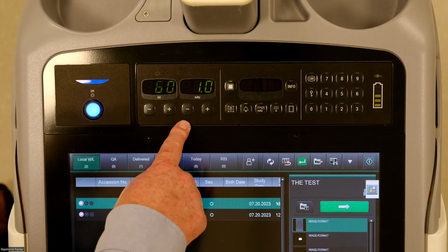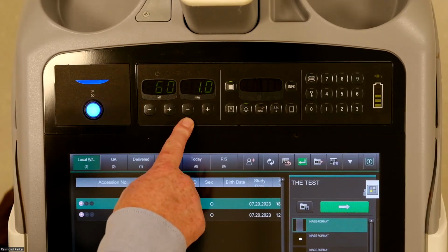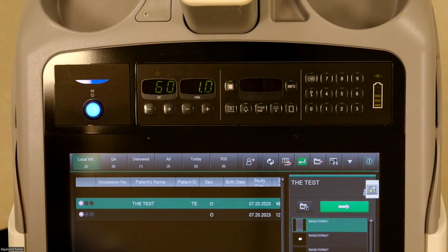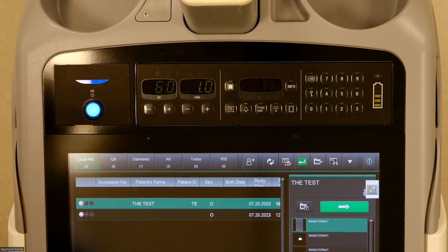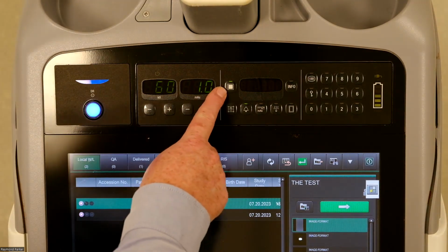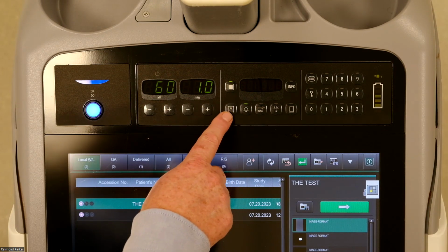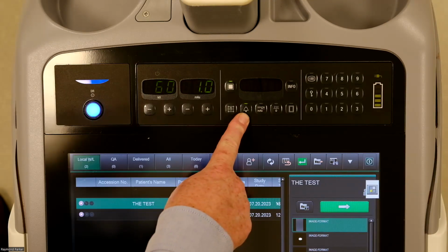Our systems for the FDR Go Plus are driven by anatomical programs. Our anatomical program list is about 400 codes deep. Usually we only build our menus up to about 250 APR codes. So above 300, should you need to create an APR code, would be available for you. You have your small and large focal spot indicator, your collimator light icon here for toggling your collimator on and off, and your sound icon here.